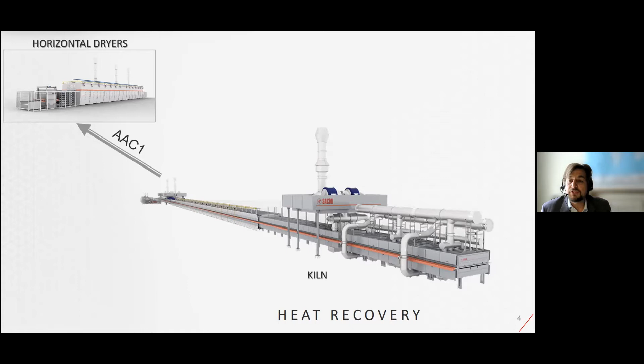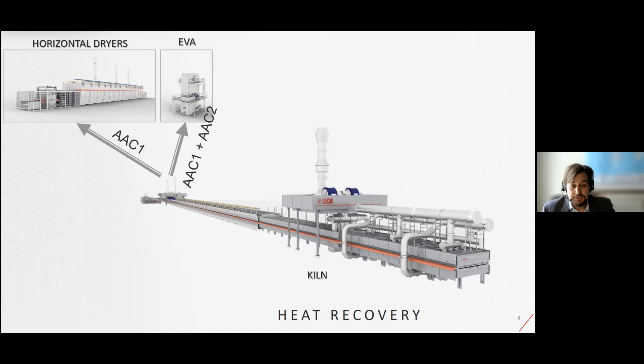This is because the heat generation of this dryer takes air from the environment, therefore at an average temperature of 25-30 degrees. The other type of recovery is recovery to the spray dryers. Sacmi has been developing such solutions for several years, providing them with an automatic regulation system to ensure high efficiency. As in the case of vertical dryers, the spray dryer can accept air coming directly from the AAC1 and AAC2 chimneys, of course subject to modification in order to receive the heat recovery. In fact, the spray dryer burner takes air from the environment and brings it to a working temperature of around 600 degrees.